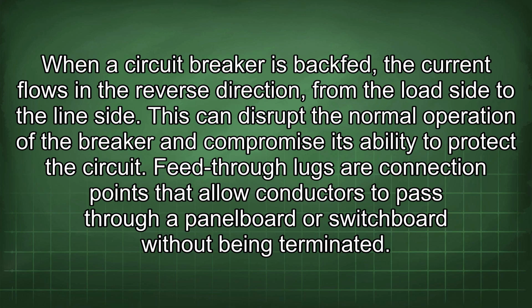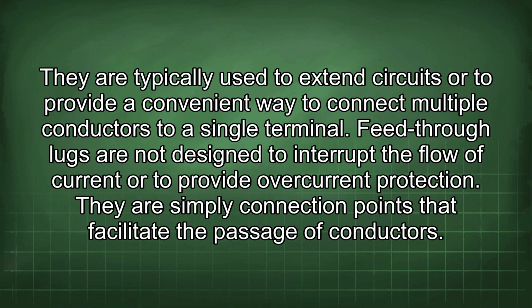Feed-through lugs are connection points that allow conductors to pass through a panel board or switchboard without being terminated. They are typically used to extend circuits or to provide a convenient way to connect multiple conductors to a single terminal. Feed-through lugs are not designed to interrupt the flow of current or to provide overcurrent protection. They are simply connection points that facilitate the passage of conductors.